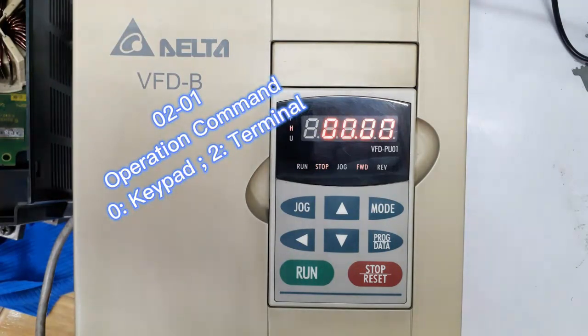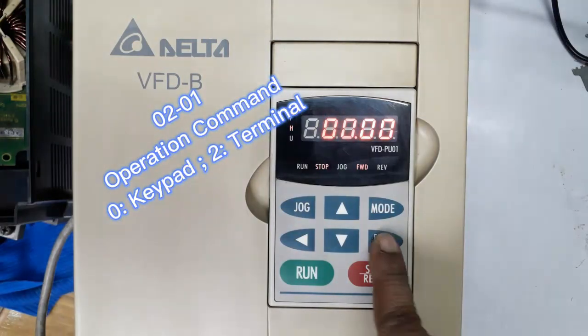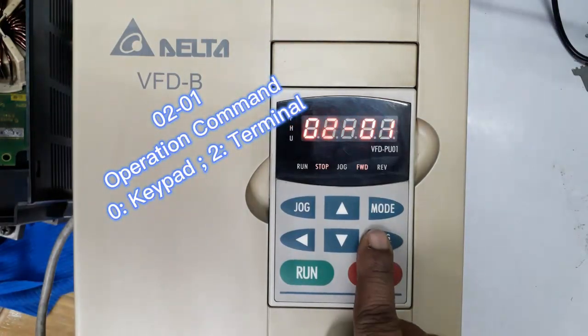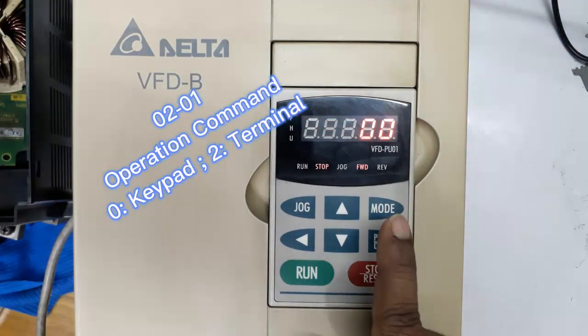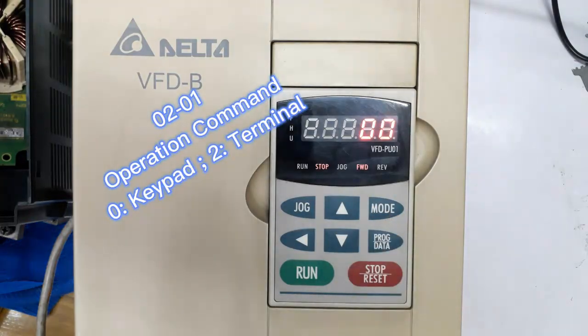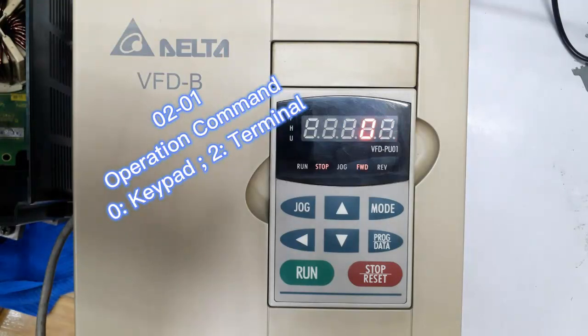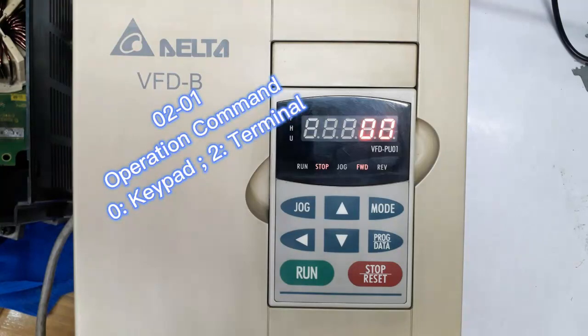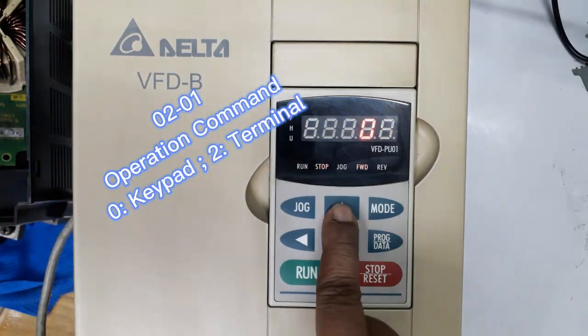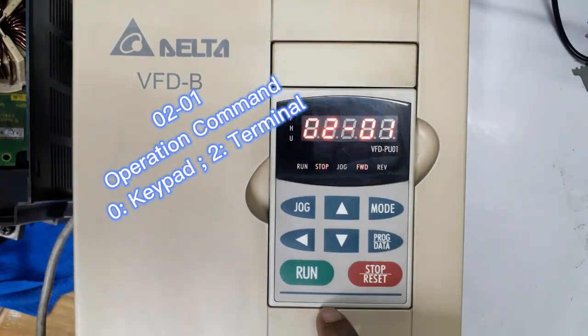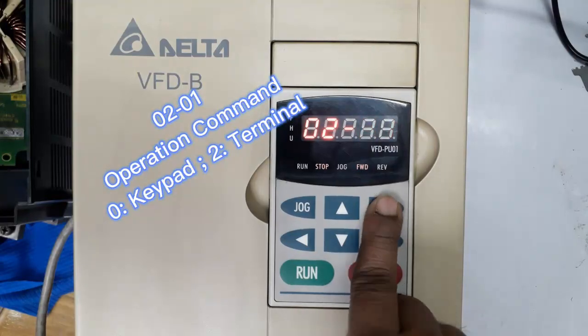So now we change the operation command from keypad to terminal. Enter into parameter 2-01. Here 0 means activate keypad run command. We want to run this drive by terminal switch, so set here 2.